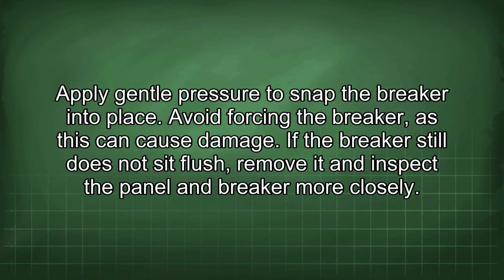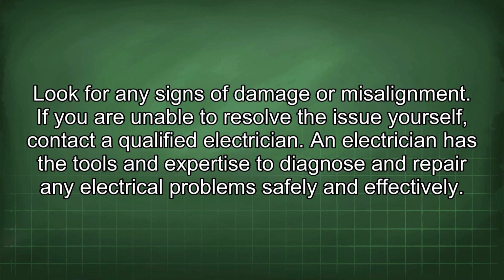If the breaker still does not sit flush, remove it and inspect the panel and breaker more closely. Look for any signs of damage or misalignment. If you are unable to resolve the issue yourself, contact a qualified electrician. An electrician has the tools and expertise to diagnose and repair any electrical problems safely and effectively.